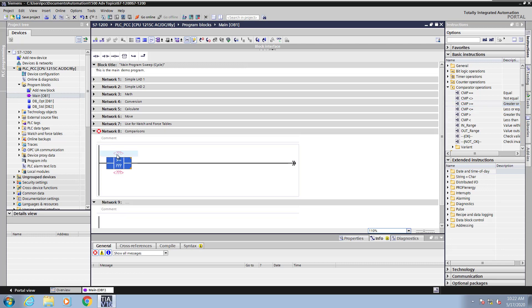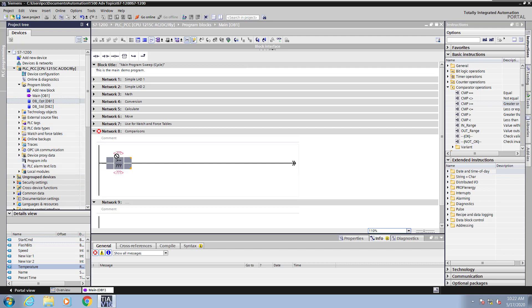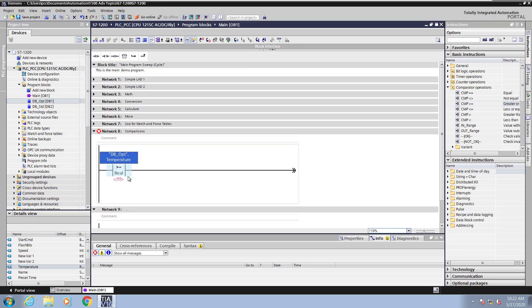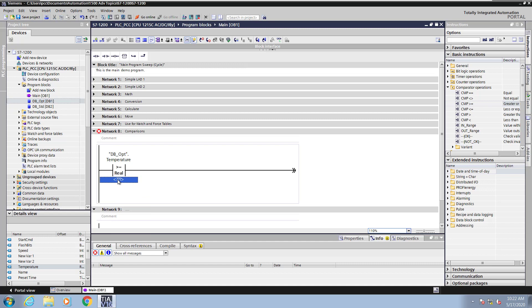In the project tree, I am going to select the optimized data block, and then I'm going to take the temperature value and drag that on top of the comparison instruction. So this is going to be the element that we're going to compare. You can select a different data type if you'd like for the comparison, but this is going to be a real. And then I'm going to enter in the value that I'm going to compare the temperature against, so 100.0.